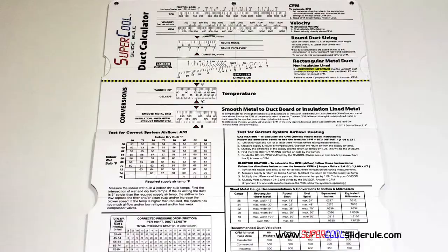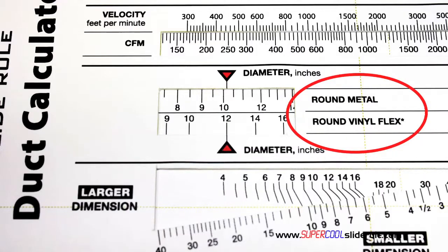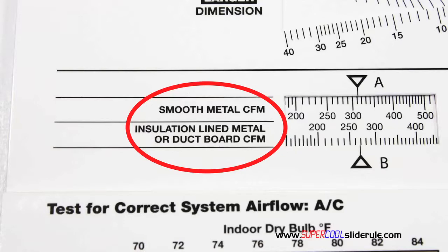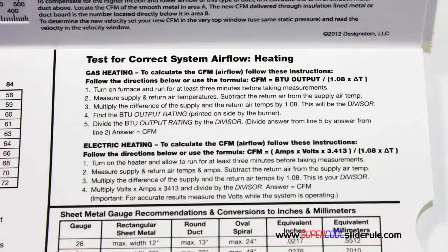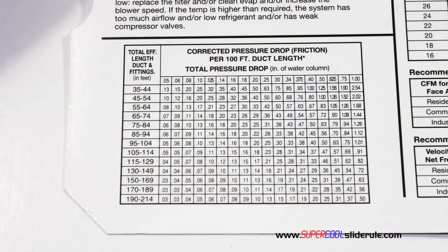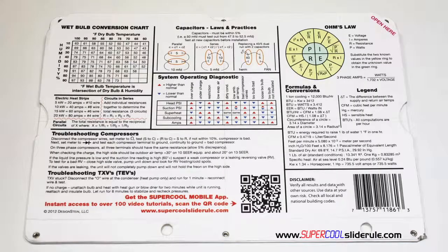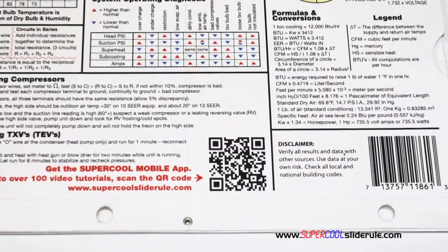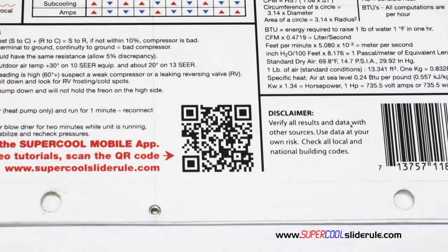Inside is packed with even more information. It performs sizing of both metal and flexible duct, and has the only direct reading conversion from smooth metal to insulation-lined metal we've ever seen. The majority of technicians have never been taught that if insulation is on the inside of the ductwork, you cannot size it with a regular duct calculator. It has step-by-step directions for determining airflow through a gas furnace, electric furnace, or an air conditioning unit. It has pressure drop multipliers for ductwork as well as recommended velocities. And finally, scanning the QR code gives instant access to over 100 tutorials to assist the technician with every test and repair imaginable.